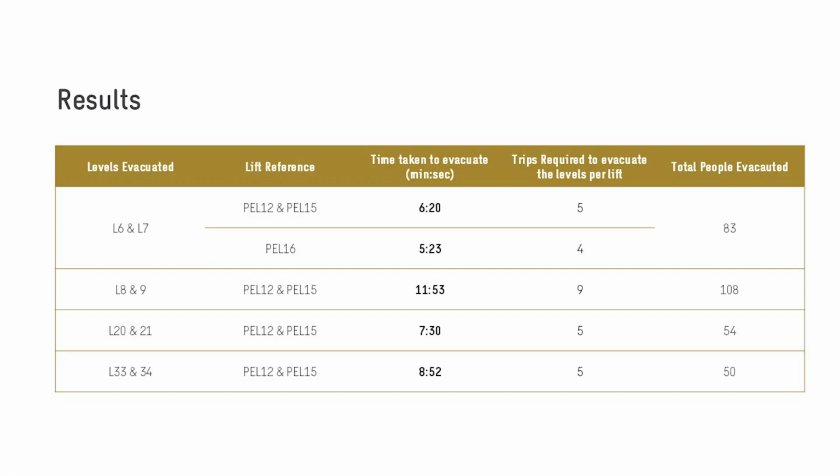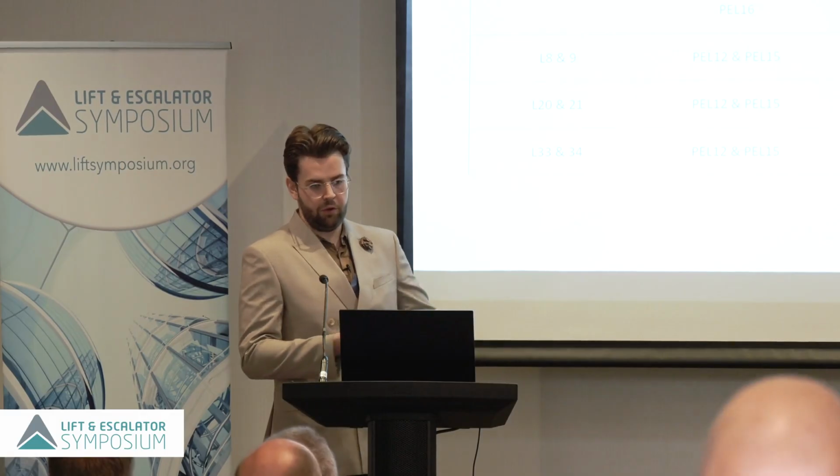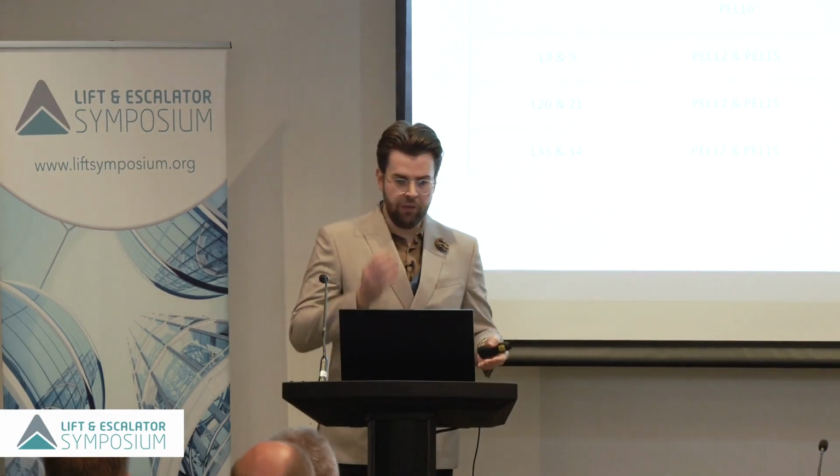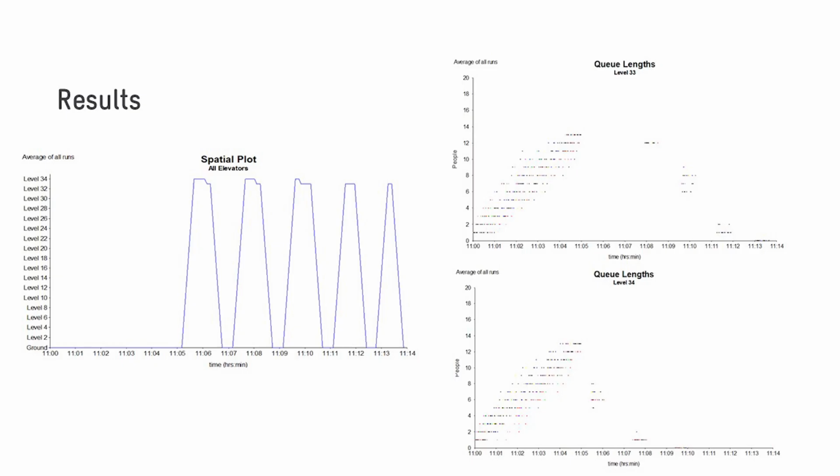So the results. We're looking anywhere between sort of 5.5 minutes and 12 minutes, and that's obviously a function of the amount of people that are required to be evacuated, the corresponding available car area, and the number of trips. And here we can see we've got our graphs.